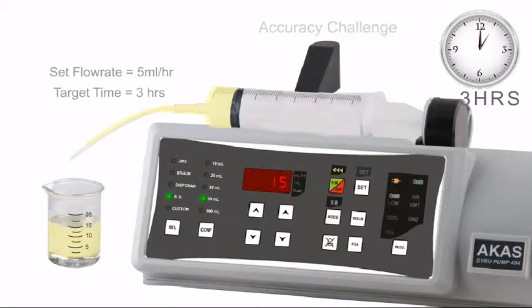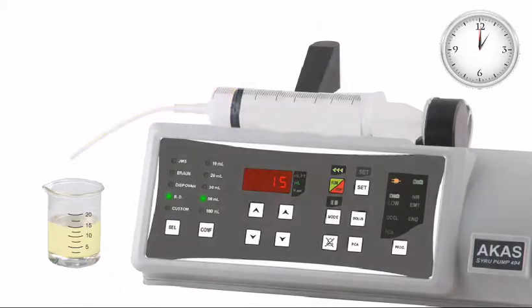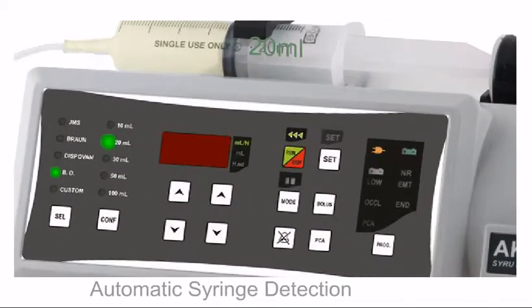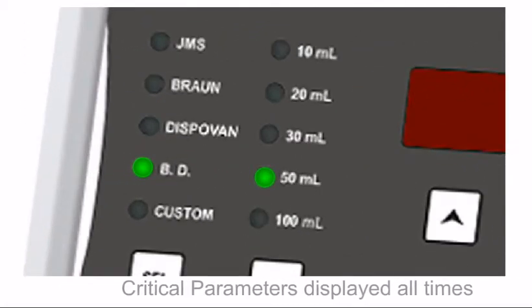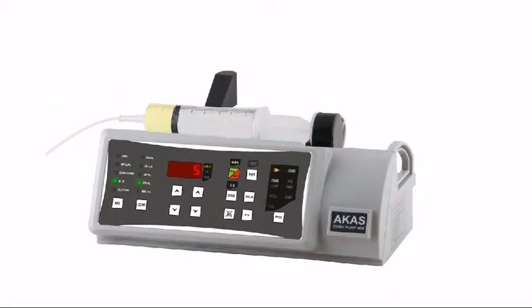AKAS's products have a proven track record since 1996. AKAS's syringe pumps can automatically detect the size of the syringe used, thereby avoiding manual wrong selection. As brand selection and syringe size selection are very critical to maintain accuracy, it is important to display the same on screen at all times for user verification.